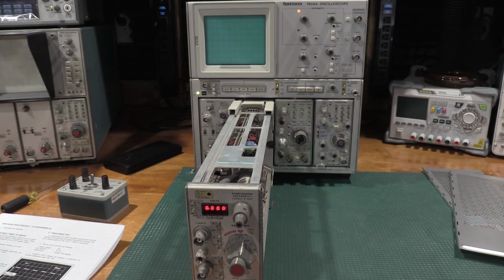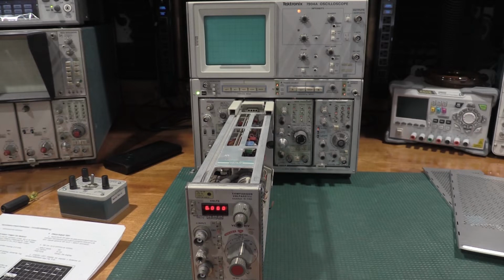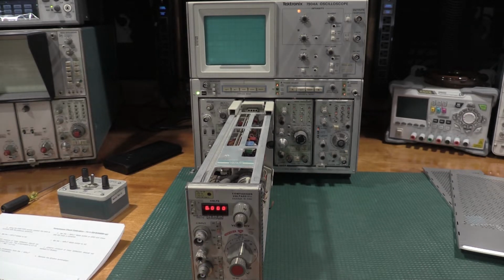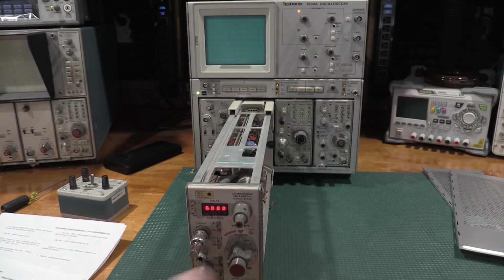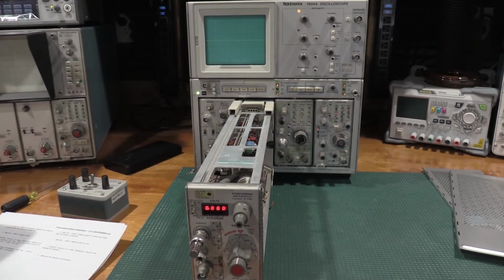and we can go right to step 8, which is checking gain, which is fine. Okay, so first things first, we're going to check drive current. And for this, I need a 50 ohm terminator. So we have a straight 50 ohm termination that goes on the plus side, which is fine. We're at 1 millivolt per division. That's in and that's in. And those are both set to ground. Give me some brightness. There we go.